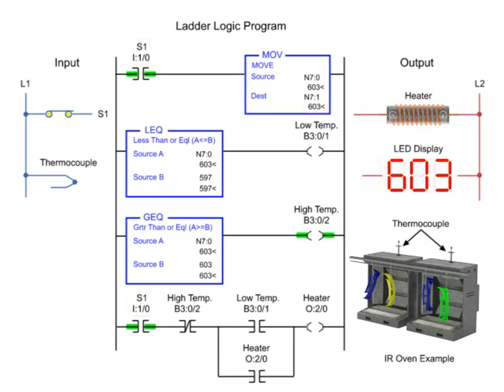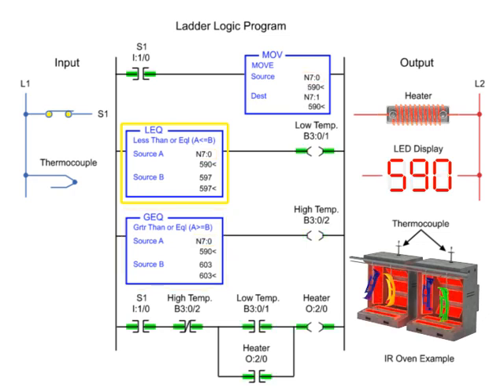Using the less-than-or-equal-to and greater-than-or-equal-to instructions addressed to the same integer file, the source values of A and B are compared to control the heater. With source A less than source B of the less-than-or-equal-to instruction, the low temp and heater outputs are enabled.